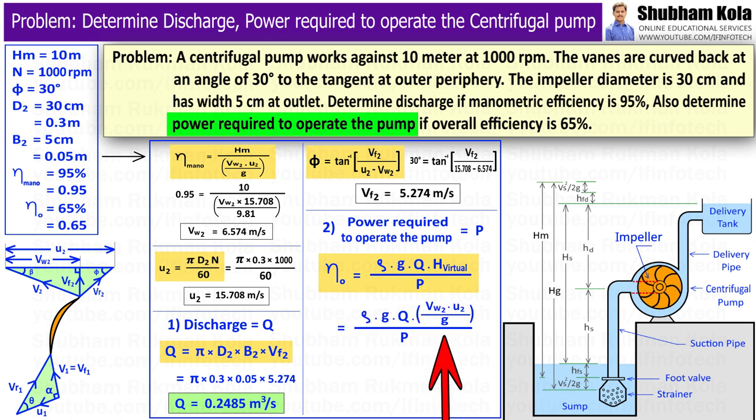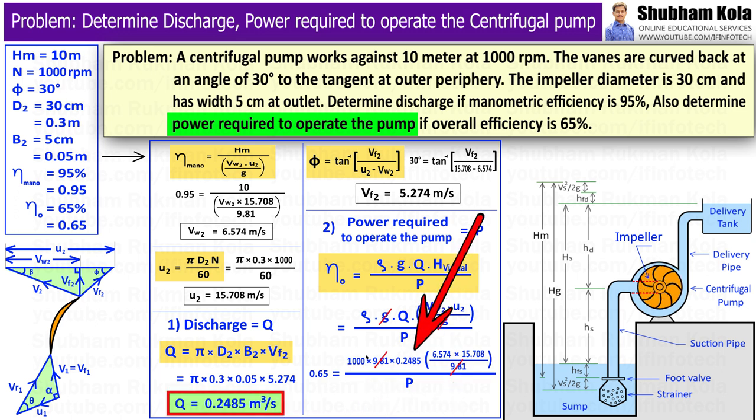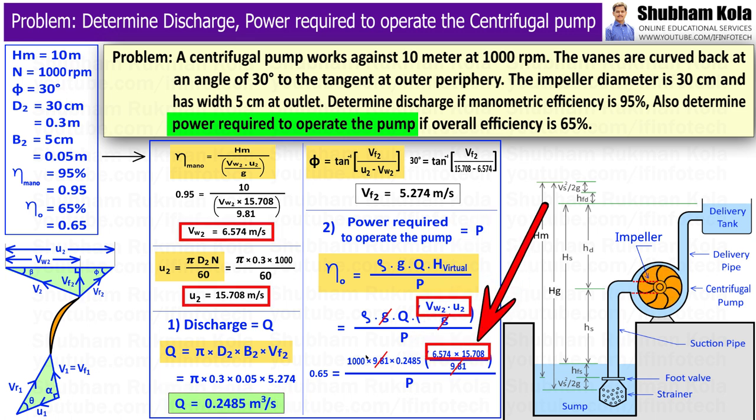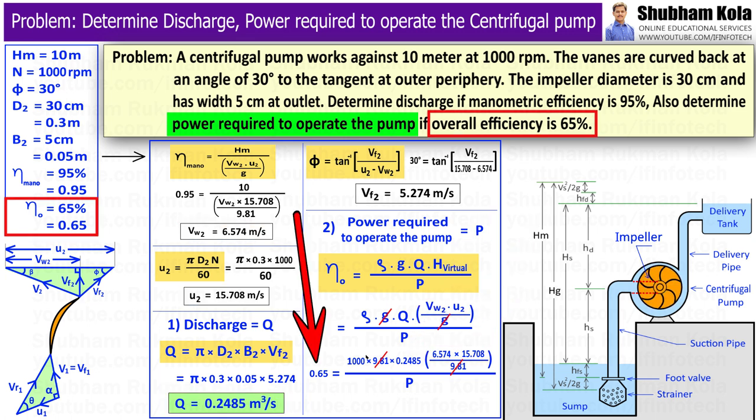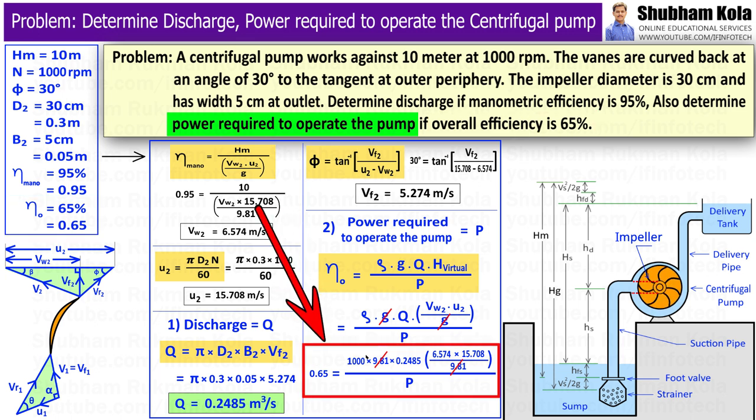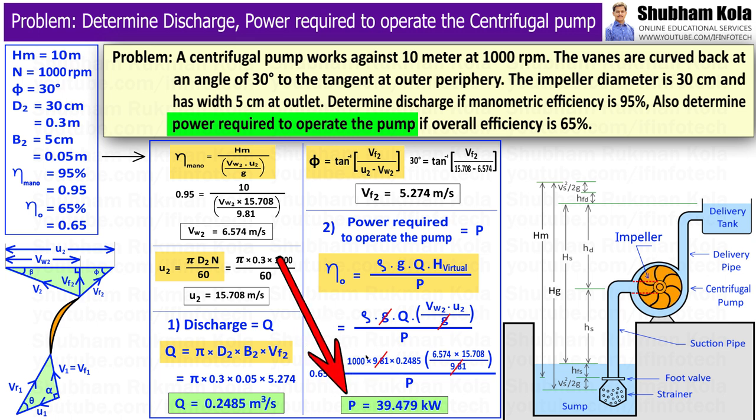Therefore, the formula of virtual head becomes Vw2 into U2 divided by g. Here, g gets cancelled and the values of Q, discharge rate, and Vw2 and U2, we have already calculated, and overall efficiency equal to 0.65. Therefore, by substituting all these values, we will get power required to drive the centrifugal pump as 39.479 kW.